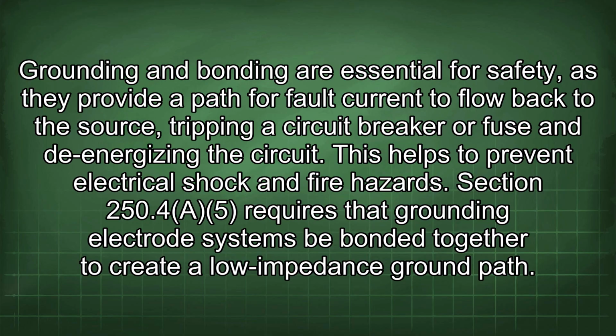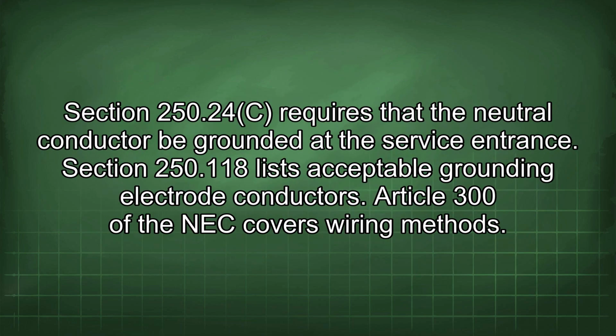Section 250.4(A)(5) requires that grounding electrode systems be bonded together to create a low-impedance ground path. Section 250.24(C) requires that the neutral conductor be grounded at the service entrance. Section 250.118 lists acceptable grounding electrode conductors.